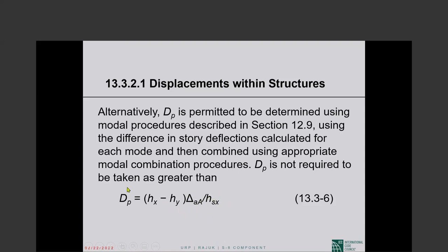So the actual relative displacement D sub P need not be taken any greater than delta allowable deflection, let's say 2% of story height. So delta sub A would be 2% of story height, divided by story height, gives us 2%. So D sub P need not be taken any larger than 2% of the vertical distance between the points where the piping is attached to the structure.